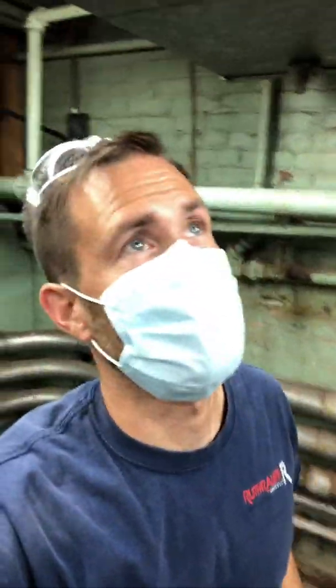Okay, we have a boiler. We have the flue piping. What is this? See that? That's a hole right on top. Right on top. There's one — I'm shutting down that boiler.